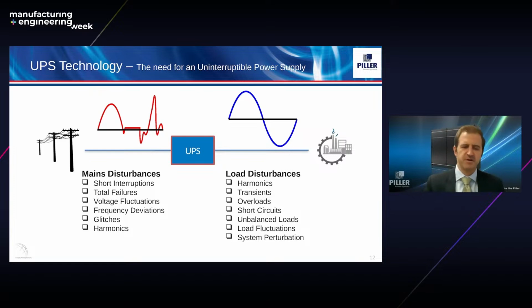They also offer isolation of your loads from the grid. So loads such as variable speed drives, large motors, fans - these can impose harmonics or draw power with a really poor power factor from the incoming supply. These issues can all add to the grid supply problems you're already starting to experience and worsen the effects of them eventually.